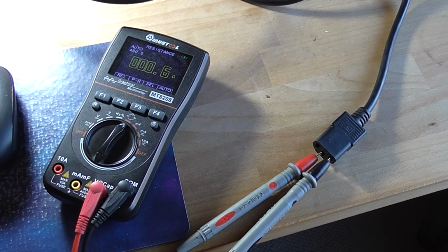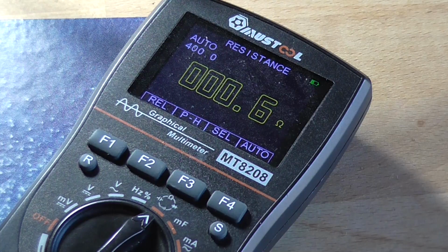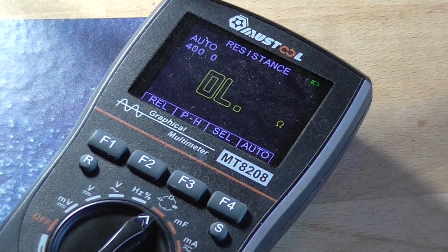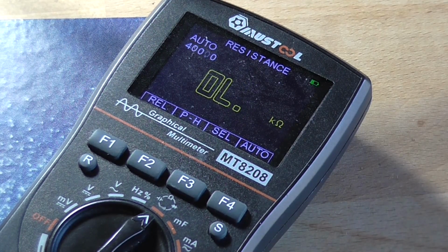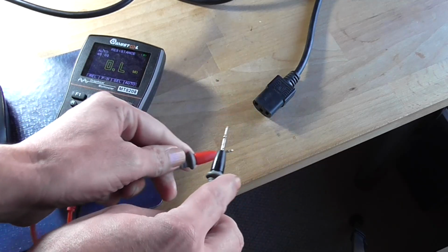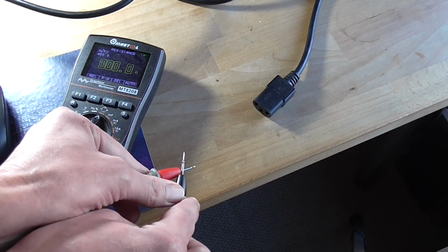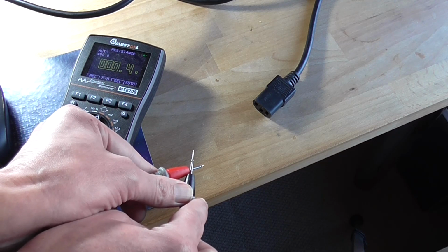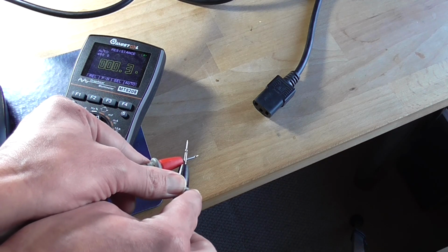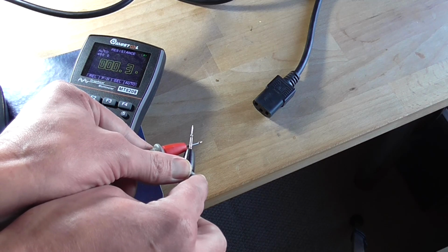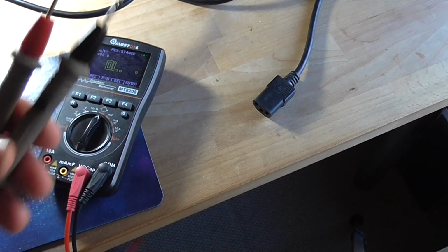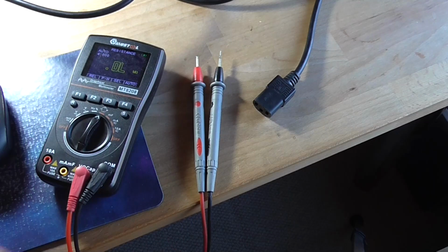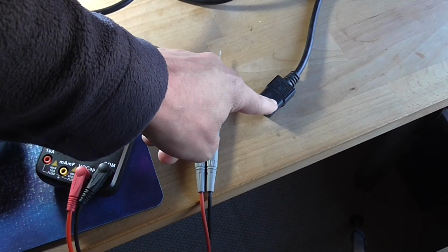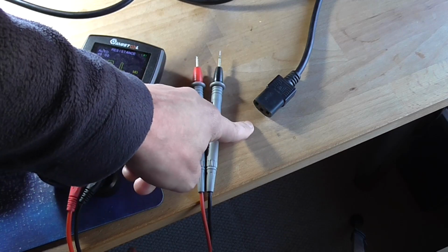And as we can see, there is a tiny bit of resistance there. It's moving up and down a little, but there could be a little bit of resistance across the probes as well. So I'll turn it off. And as we can see, it just goes back to open load. So just to find out what our resistance across our leads are, yeah, about the same as what we were measuring across the plug, about 0.3 of an ohm and jumping around to 0.5 of an ohm. So the leads are introducing a little bit of resistance into it. So we can see that electrically there's close to 0 ohms between neutral and earth.